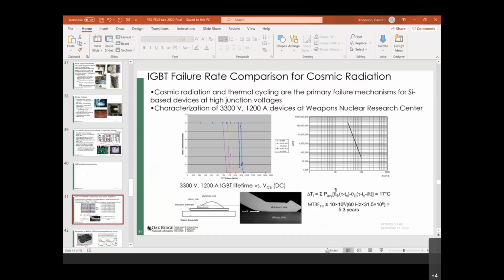So we have some data on that. A couple of possible things can happen. One is that whenever an event is detected that requires the modulator to shut down, we shut down very quickly. That can occur at any point during the switching cycles of the IGBTs, and we don't know what the peak collector current will be at that time. If it's high enough, the parasitic inductance in the bridge can create quite large overvoltage events. That's a pretty abnormal condition, but we do it to protect the klystron, because we don't want the IGBTs continuing to pump energy out to the shorted load.